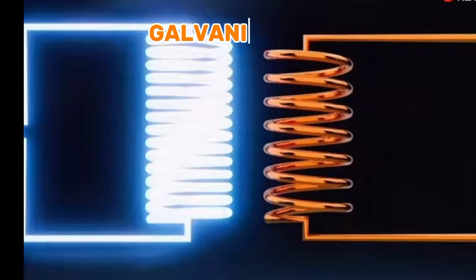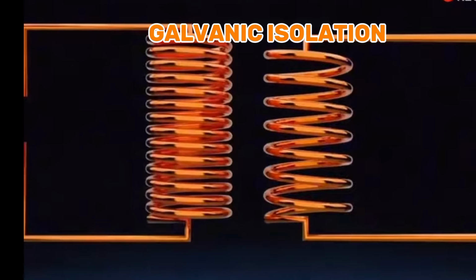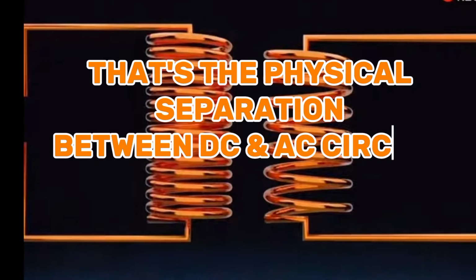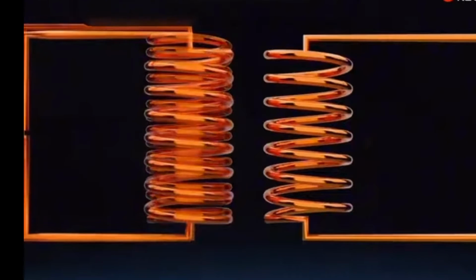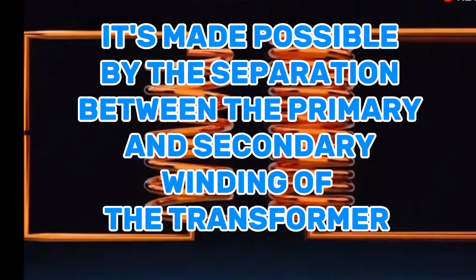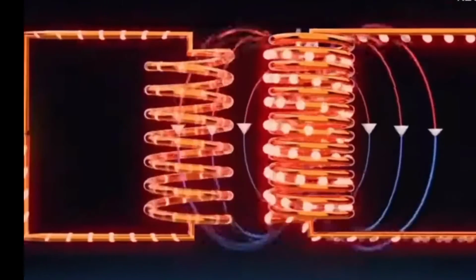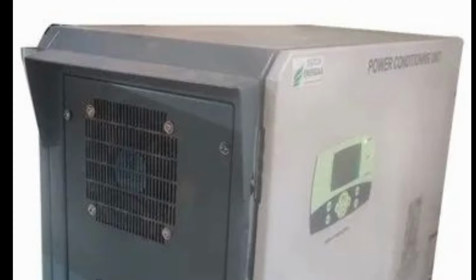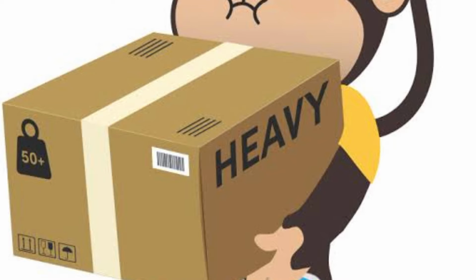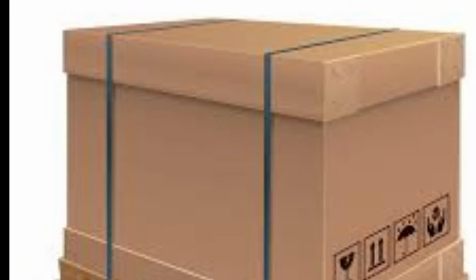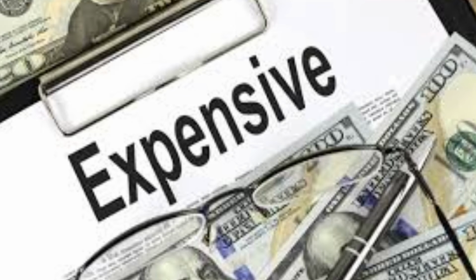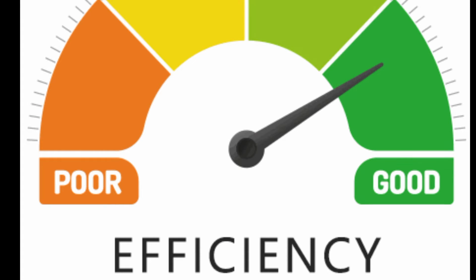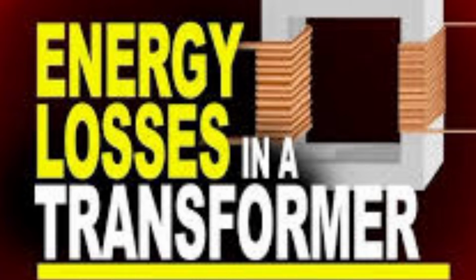But here's the cool part: transformer-based inverters also provide something called galvanic isolation. This separation is crucial for safety, especially if you're dealing with sensitive electronics. It prevents dangerous voltage spikes from frying your precious gadgets. Think of it as an extra layer of protection against the unexpected. However, this robustness comes at a cost. Transformer-based inverters tend to be heavier, bulkier, and a bit more expensive than their transformerless counterparts. Plus, those big transformers can be a bit inefficient, losing some energy as heat.